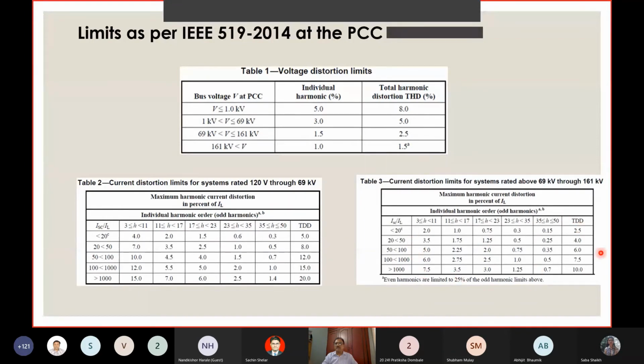Same ratios, but 2.5, 4, 6, 7.5, and 10. Because as the kV increases, the impedance decreases. So the source becomes stiff. So these limits are achievable. So we are discussing with many industries in 11, 22, 33, as well as 110 kV, where we are able to give them what is their limit. For example, in Tamil Nadu, which is the only state which has gone for harmonic penalty.